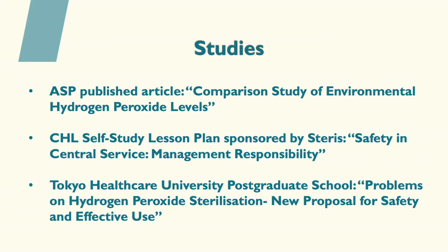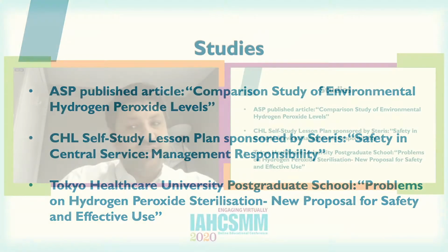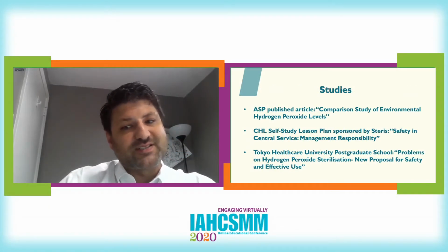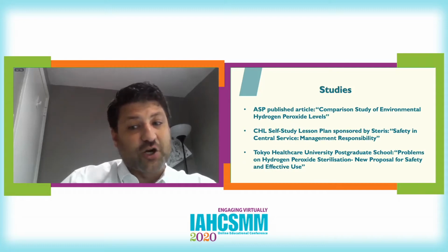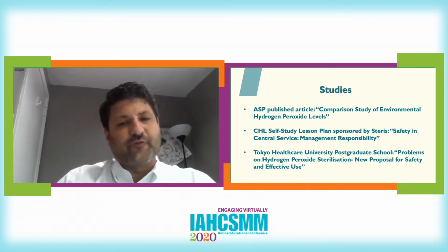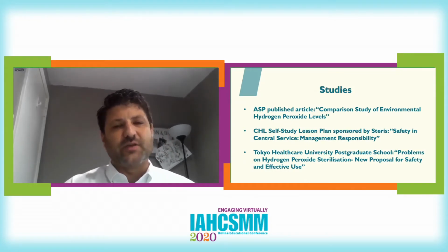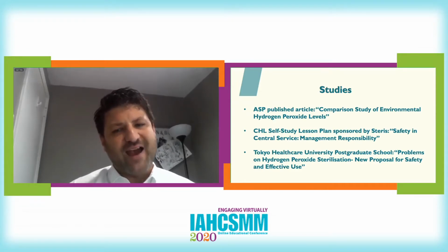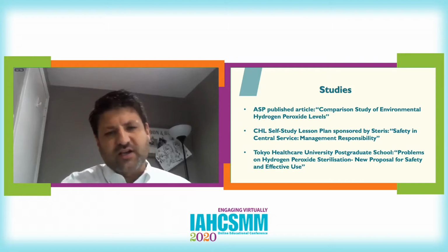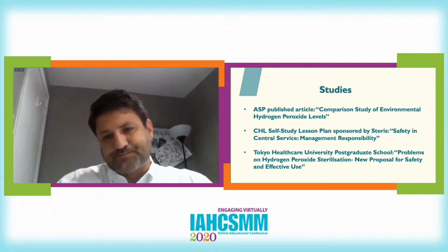They also found that the sterilized products continue to off-gas hydrogen peroxide after they've been removed. Off-gassing of sterilant gas is well known for ethylene oxide, but the study concluded that the same issue may occur with hydrogen peroxide. We've been a little bit familiarized with that recently because there's been some talk of that with N95 masks. But what if it wasn't just N95 masks?